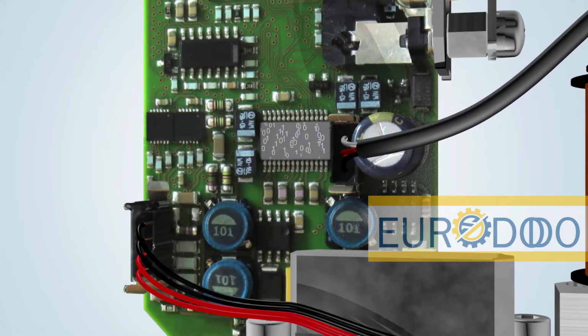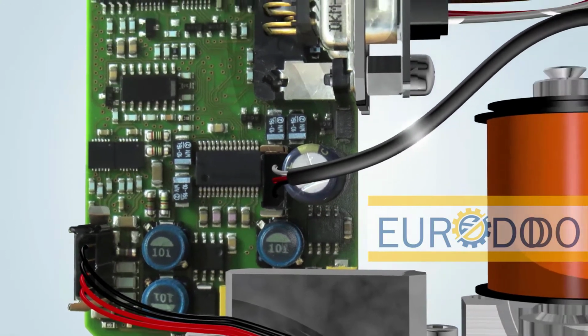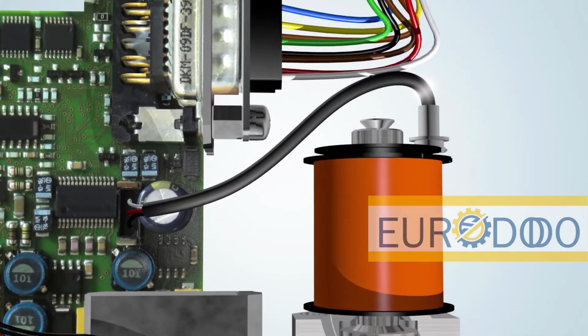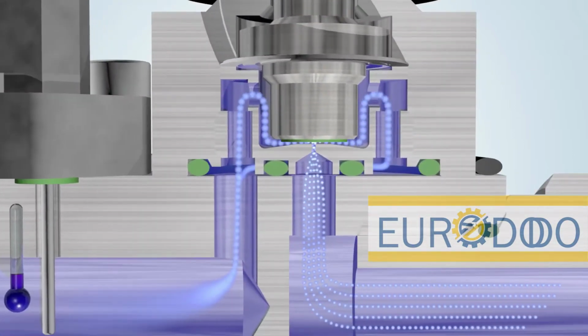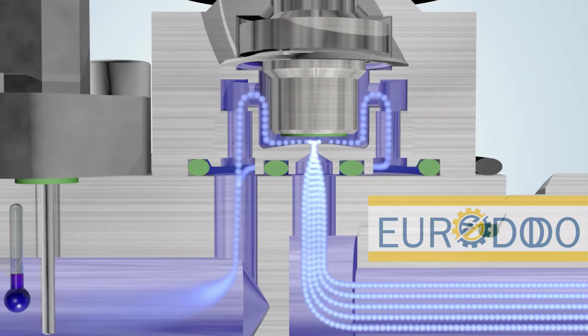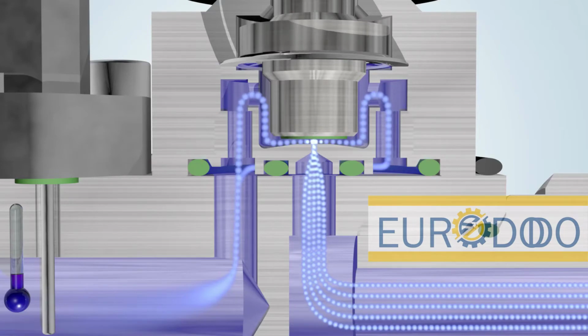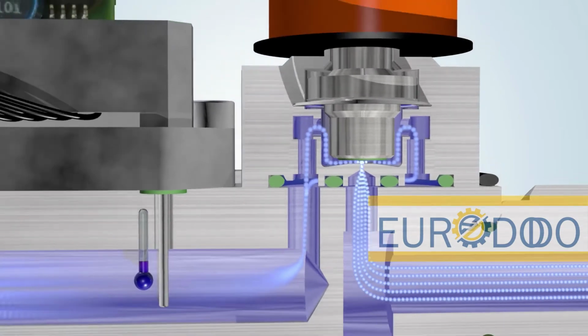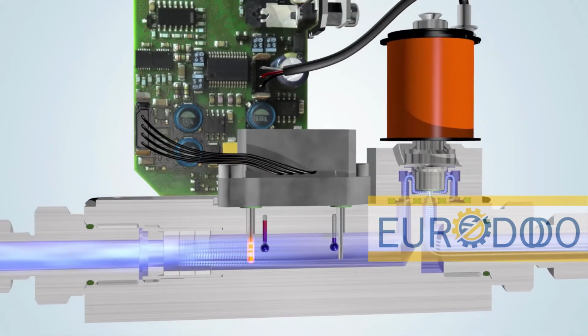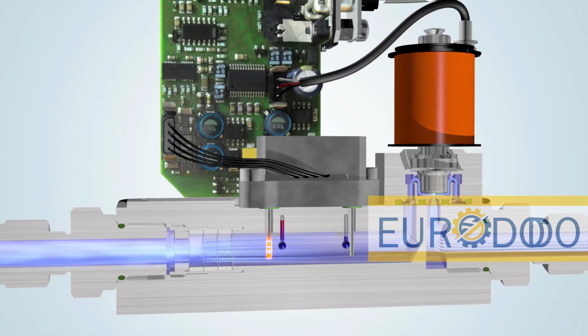The signal from the sensor is compared with the desired value in the microprocessor. The electric current of the coil is adjusted so that the distance between the plunger and the orifice is exactly right for controlling the desired quantity of gas. The control circuit performs this operation in a few milliseconds. In this way, a very constant and stable flow of gas is achieved.